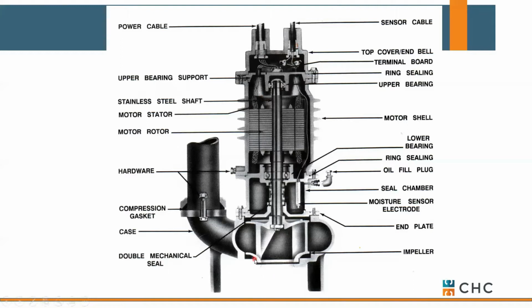Okay. Notice this particular pump has a very tall impeller in it. Obviously, we have the potential to pass good-sized solids through here as well. The fact that this pump has feet on it would indicate it's a foot-mounted or floor-mounted unit. Maybe not designed for a removal system. We'll talk about that in just a minute. But this is a standard submersible pump designed to pass full-size solids.